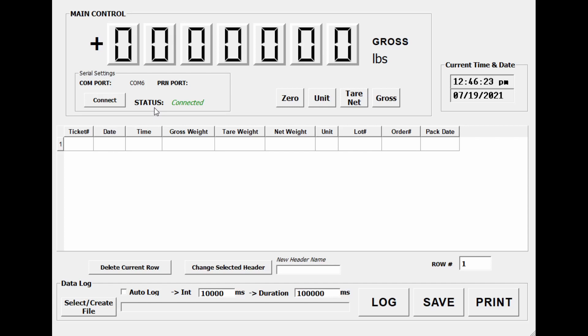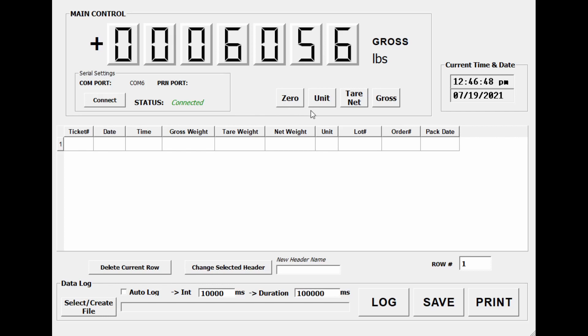You can see how my indicator actually responds. On my indicator 900, it says 6,056 pounds, and right here it says 6,056 pounds in gross mode. Actually, what I could do is actually press the zero button. Well you won't see it on the screen recording, but another pop-up menu will appear. It says you're permanently zeroing the scale, process cannot be reversed, would you like to continue? Once I click on zero, it will actually zero out not just the program, but also the indicator. When I click on it, my indicator actually went back to zero and it's the same thing here. This actually will zero out the indicator itself.